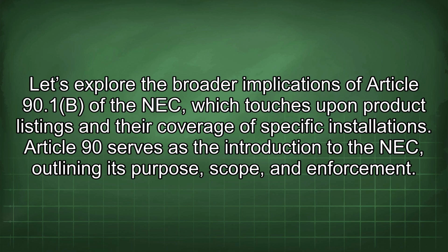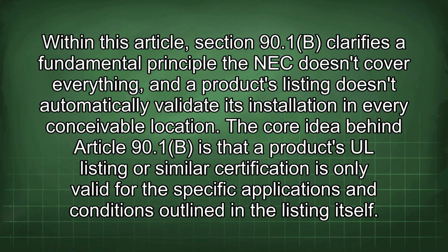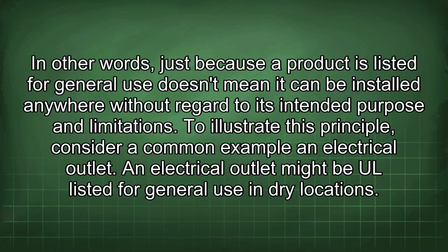Let's explore the broader implications of Article 90.1b of the NEC, which touches upon product listings and their coverage of specific installations. Article 90 serves as the introduction to the NEC, outlining its purpose, scope, and enforcement. Within this article, Section 90.1b clarifies a fundamental principle: the NEC doesn't cover everything, and a product's listing doesn't automatically validate its installation in every conceivable location. The core idea behind Article 90.1b is that a product's UL listing or similar certification is only valid for the specific applications and conditions outlined in the listing itself. In other words, just because a product is listed for general use doesn't mean it can be installed anywhere without regard to its intended purpose and limitations.